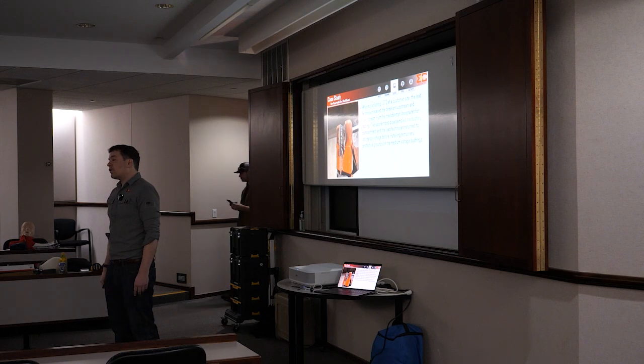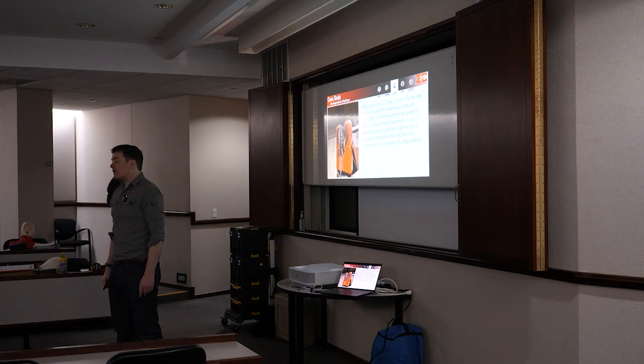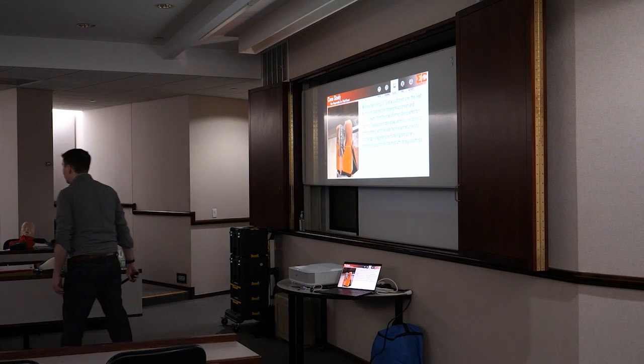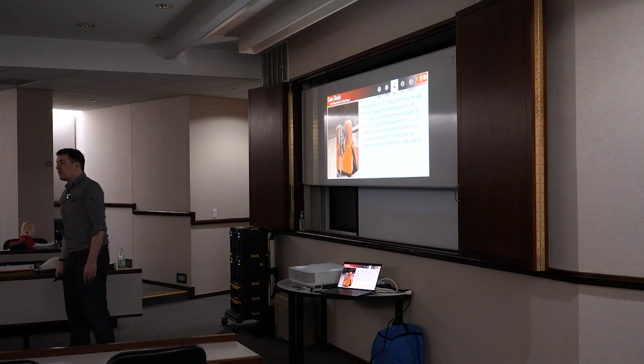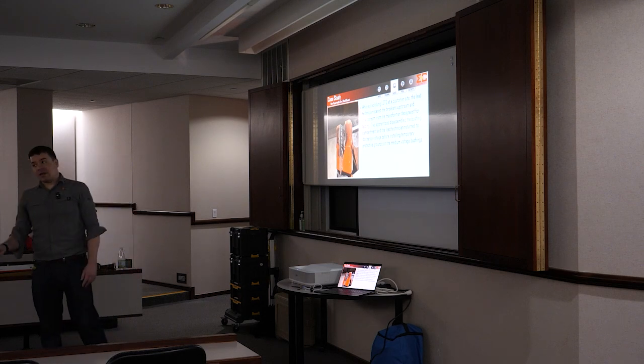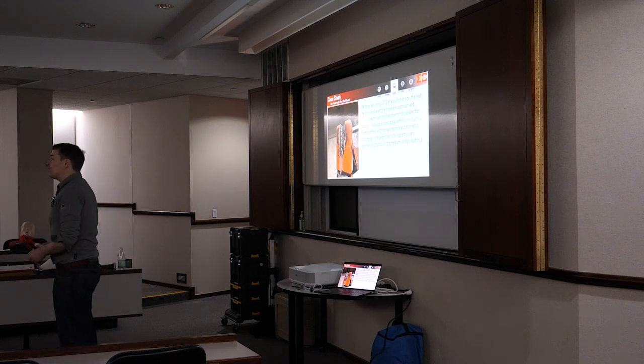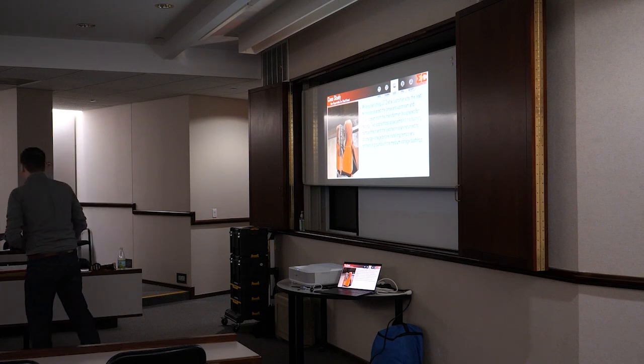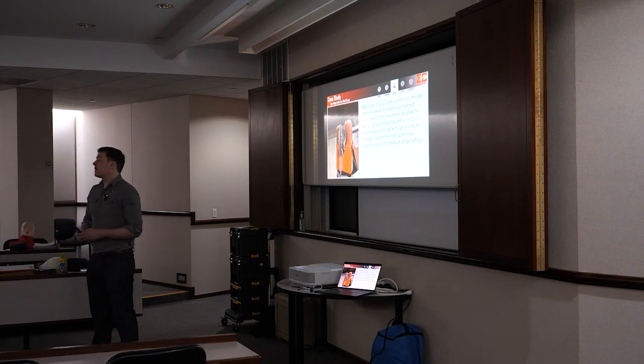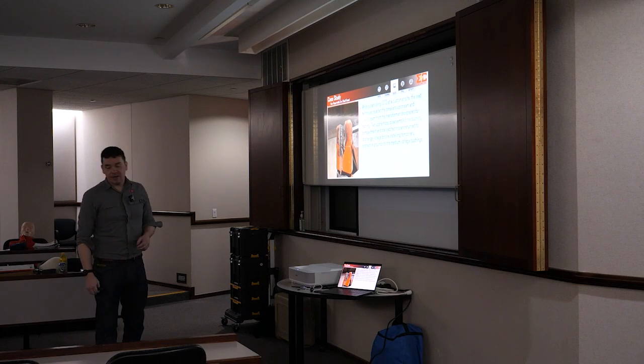Better training. Use the non-contact voltage detector, especially if you're going to put on your suit to touch something. On top of that, the 2 apprentice technicians just trusted the lockout/tagout - they hung their locks, didn't verify what we had, and started disassembling almost immediately.